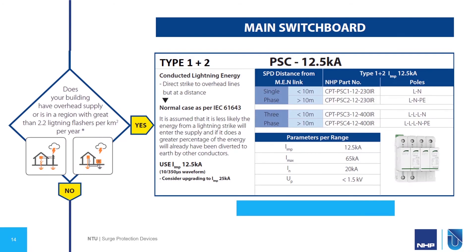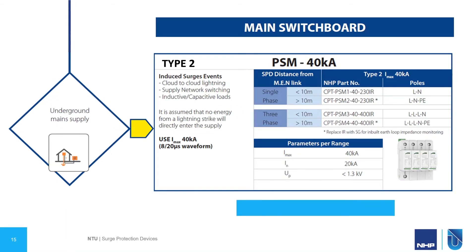It's worth noting that there's no problem with upgrading to the 25 kA unit, which may be relevant if you've got a particularly sensitive, vulnerable, or expensive installation. If that's not the case, then it's assumed that no energy from a lightning strike will directly enter your supply, and therefore you can go straight to a Type 2 device. Here, NHP has the PSM 40 kA range. There is no IIMP for this device because it's a pure Type 2. It has an IMAX of 40 kA, a nominal current of 20 kA, and a protection level of less than 1.3 kV.